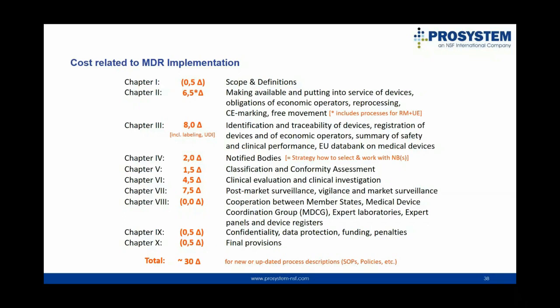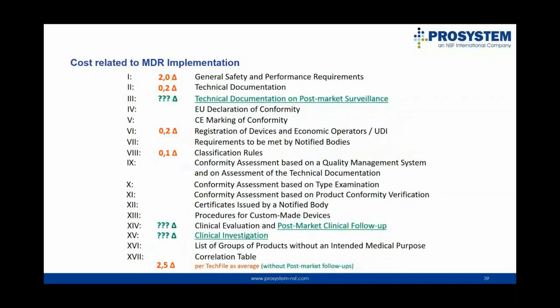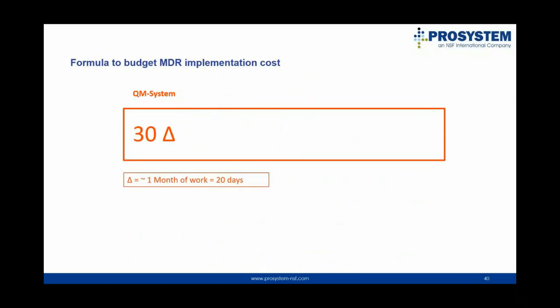Our conclusion is that we need approximately 30 work months to get all the processes in place, including post-market surveillance processes. If we look into the annexes, we can make a similar estimate for the amount of work when it comes to remediation work on technical files. So our best guess, as introduced two slides ago, is 2.5 work months. It's a good planning number. And if we conclude this, we can create a formula and say the total effort to be compliant with MDR is something around 30 deltas. Please interpret this as 30 months of work, plus the multiplication of a factor 2.5 for each technical file you have to maintain and upgrade.